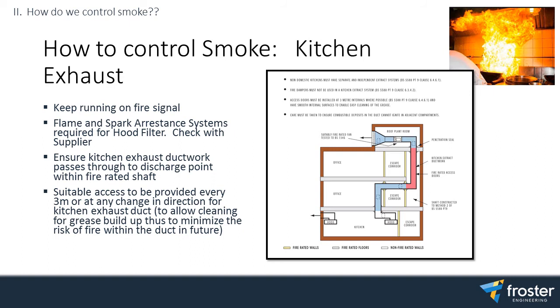Kitchen exhaust. That's another means of smoke management. The new standard 1668 2015 was adopted recently. It took over from 1998. There was a few minor changes to it. Obviously, kitchen exhaust fan, you keep it running on a fire signal as opposed to a shutdown. This has been made clearer as well. So the hood supplier needs to provide a spark arrestance system within the filter in the hood so that there's no risk of an explosive event within your exhaust path.